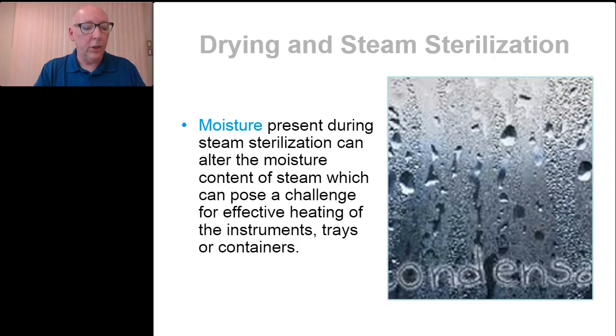And again, in addition, the sterilizer could experience condensation issues relative to moisture if there's moisture in the load prior to the sterilization process starting. So if you want instruments to be dry at the end of the sterilization process, then they need to be dry at the beginning of the sterilization process. I know those devices can be intricate, complex, so make sure they're dry. If you want those to be dry at the end of the process, let's make sure that they're dry at the beginning of the sterilization process.